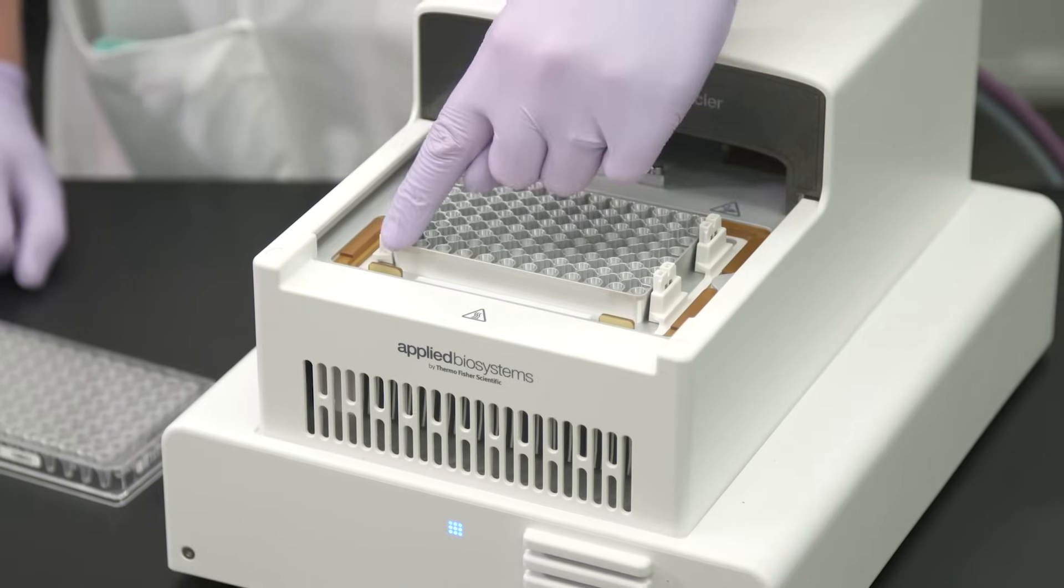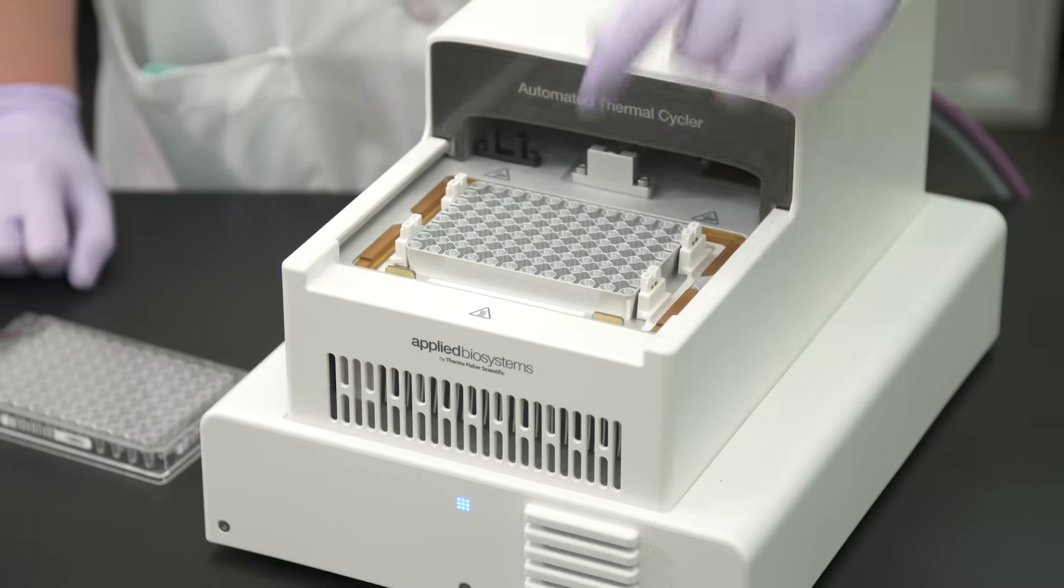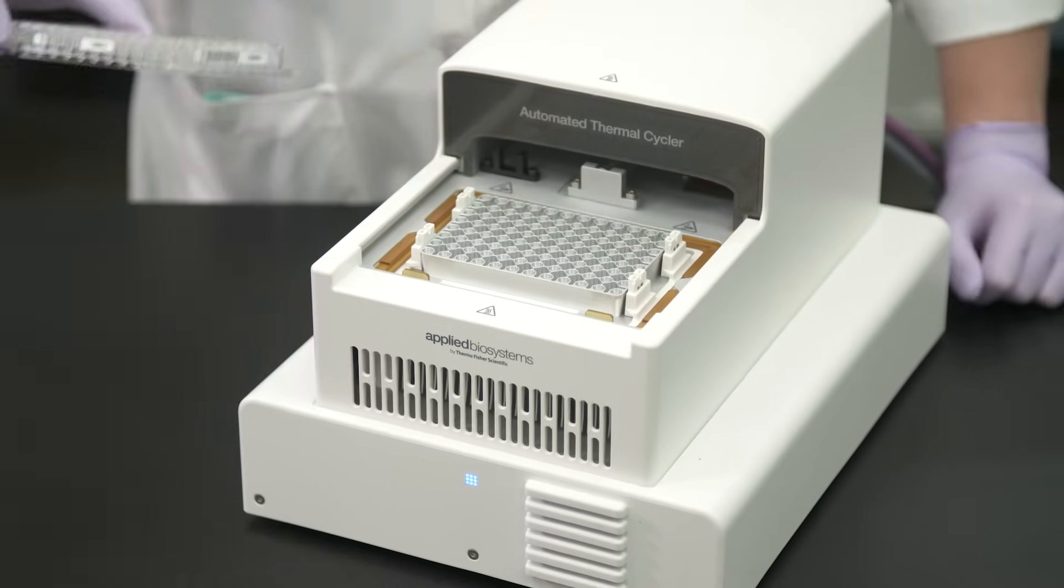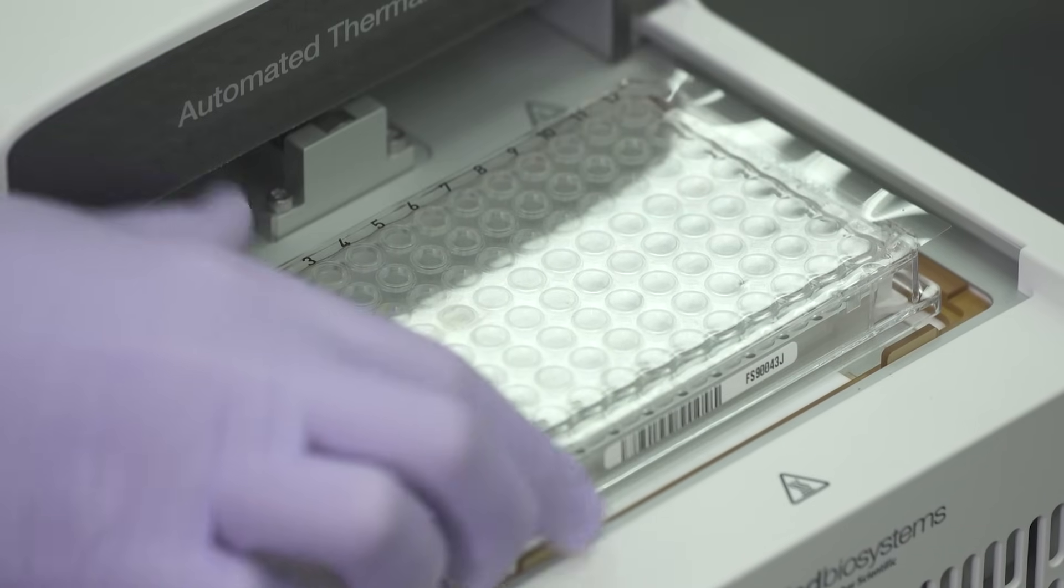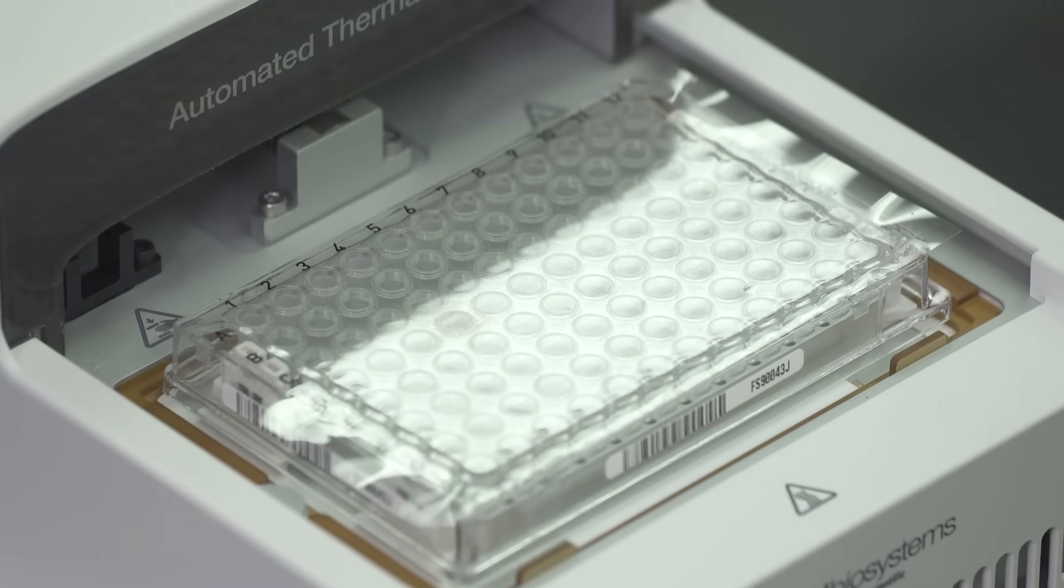The full skirted plate is designed specifically for instruments with a raised thermal cycler block. You'll see that the full skirted plate fits securely over the raised block format unlike other formats.